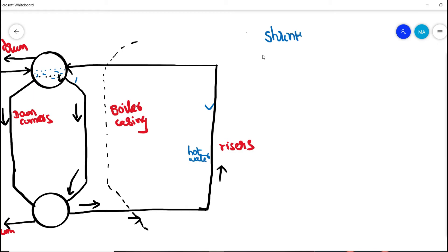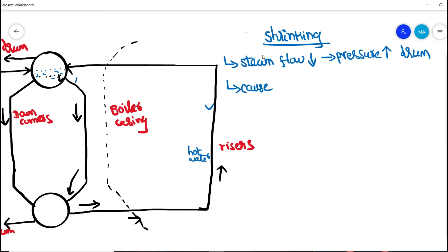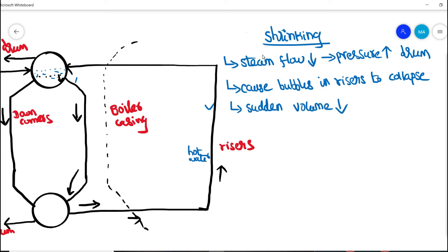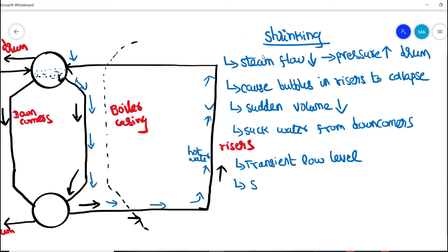Now we discuss the reverse condition — shrinking. When steam flow decreases, this causes the pressure inside the steam drum to increase. For example, when a steam turbine trips suddenly, steam flow consumption comes down, causing higher pressure inside the steam drum. This causes the hot water to collapse inside the riser — the bubbles in the hot water start to collapse — causing a sudden decrease in volume inside the chamber. This pulls the boiler feed water down from the downcomers, and water is sucked back into the risers, causing a transient low level inside the steam drum. This phenomenon is called the shrinking effect.